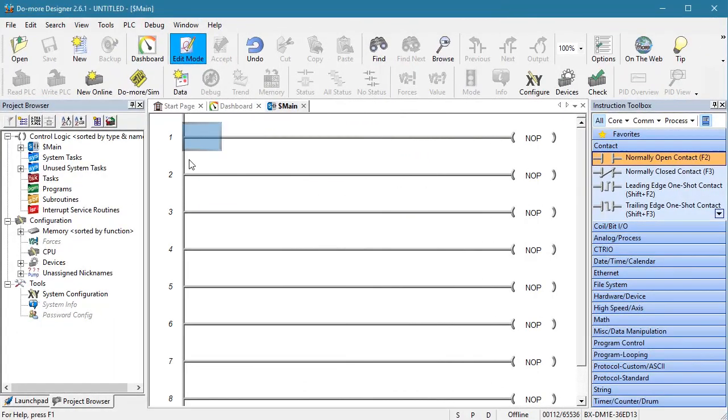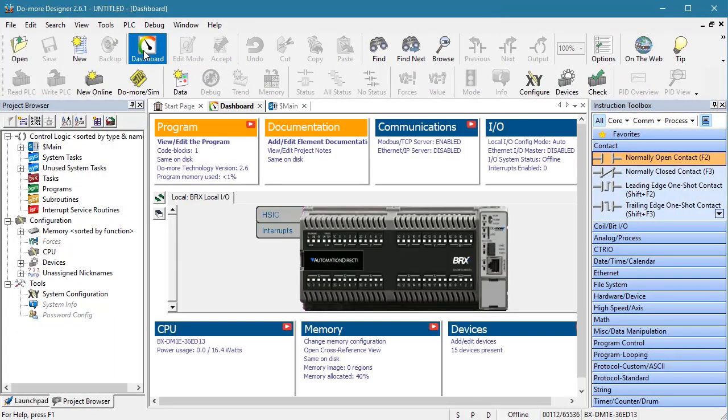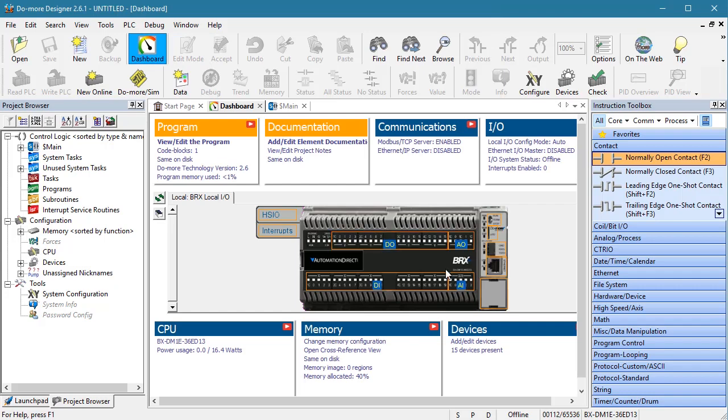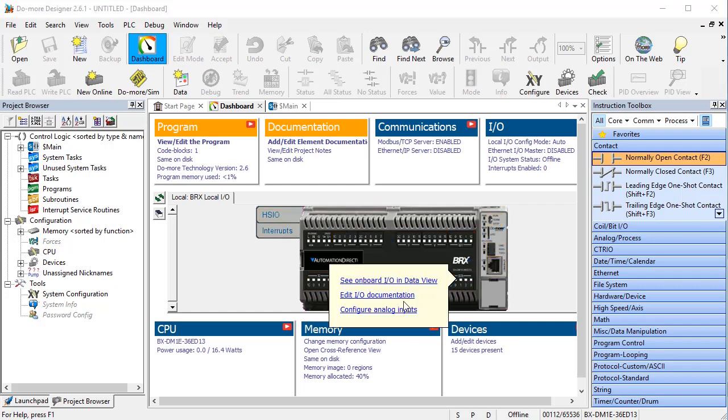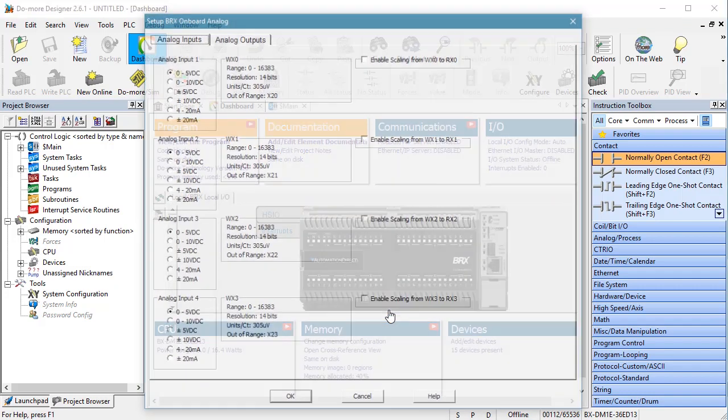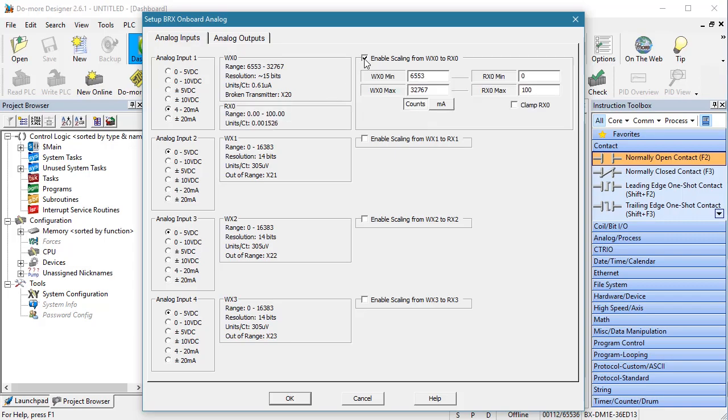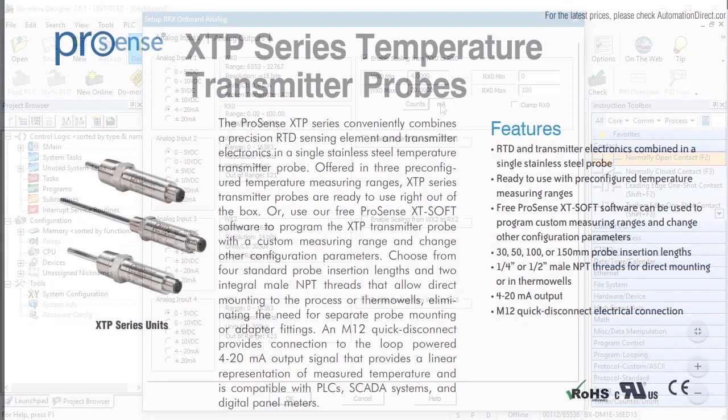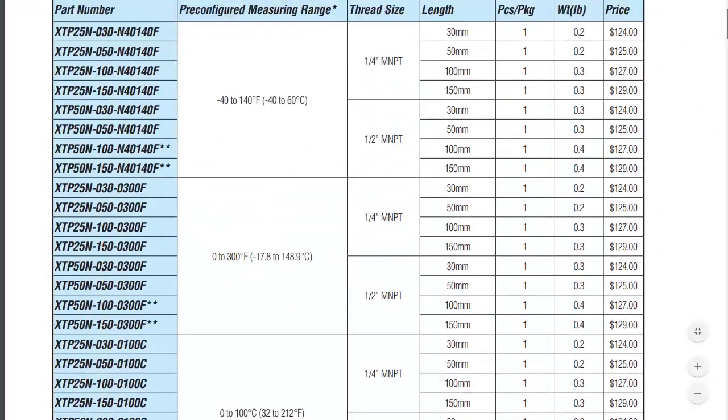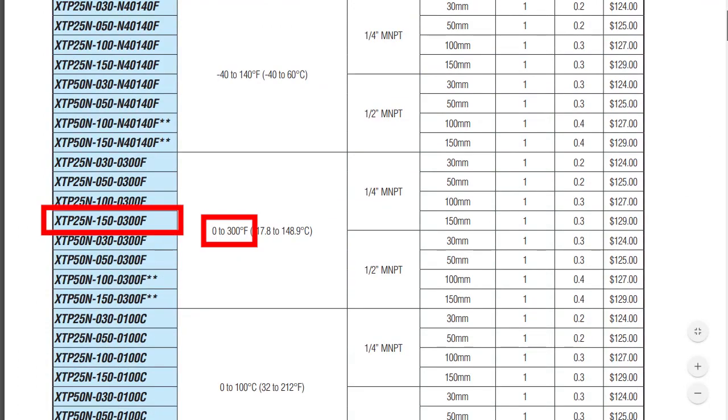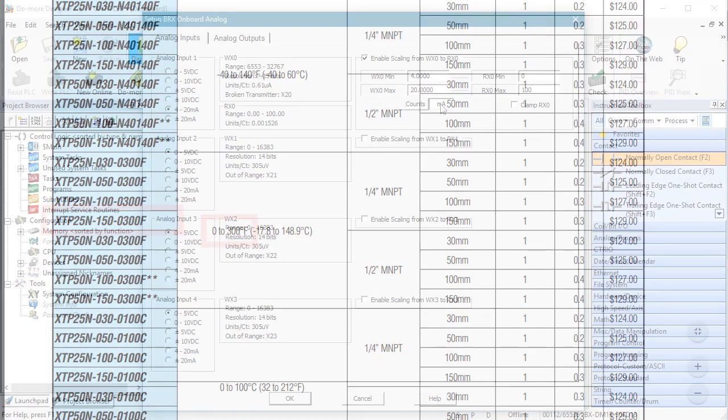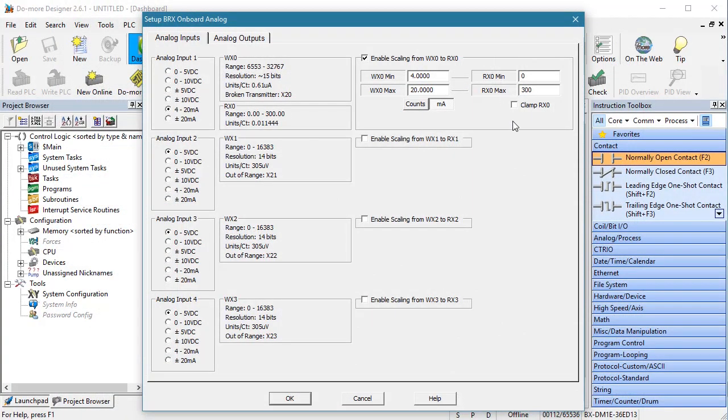To set up the analog input, go to the dashboard and configure analog inputs. We are using a 4 to 20 milliamps sensor and we do want to scale it here for 4 to 20 milliamps. The RTD sensor we are using goes from 0 to 300 degrees Fahrenheit, so we put that here.